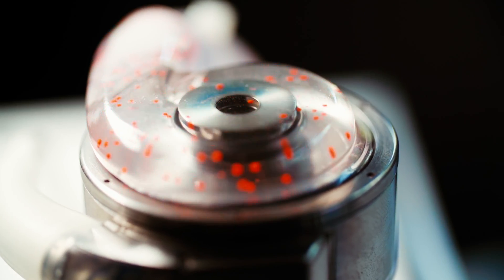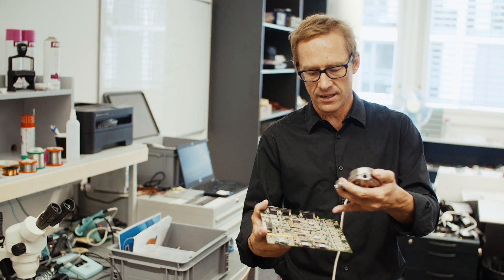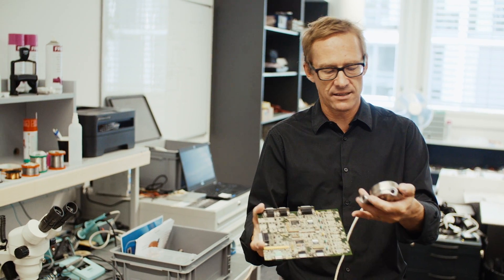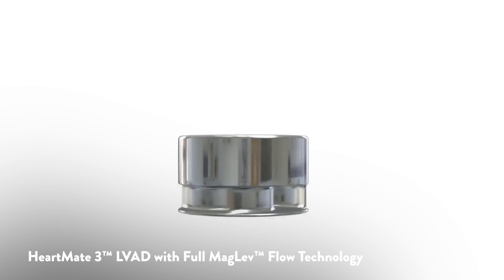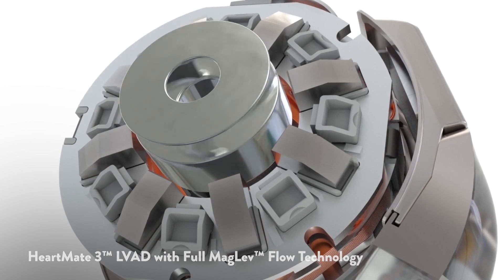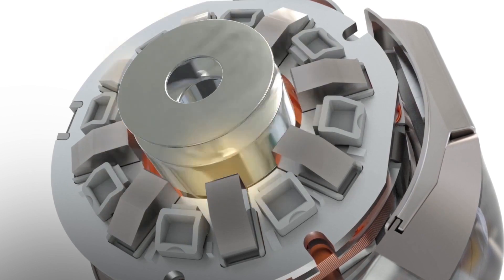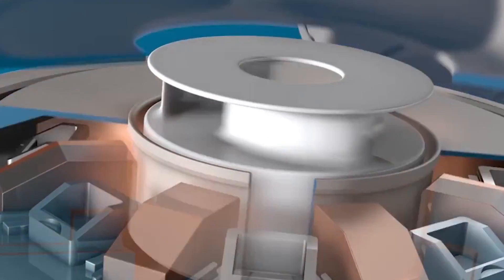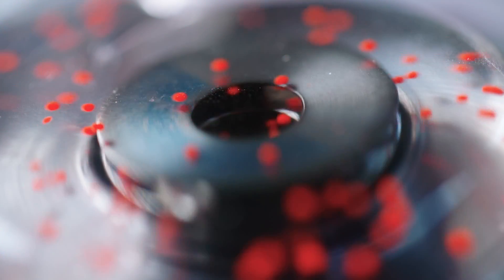Parts became smaller, much more powerful. In 2000 or so, we brought this electronics from that size into an implantable. In the HeartMate 3, we applied the right amount of magnetic forces. The gap between the rotor part — the thing that turns and the thing that stays in place — is all around the rotor. They do not contact each other. This is the perfect scenario for blood cells, and this can only be achieved if you use the full maglev technology.